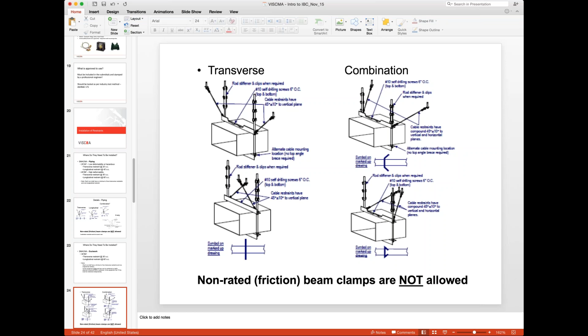So here's that discussion of rod stiffeners I was bringing up. In general, you're going to see any rods from 3/8 to 1 1/4. Occasionally you will get higher, but those are the general 90-10 rule you're going to see on your job sites. And that table shows the maximum length before you're going to need a stiffener. And so you see a 1/2-inch rod, anything over 2 feet, it's going to require stiffening, because any compression load, it's going to buckle. It almost buckles under its own weight when you stand it up vertically.